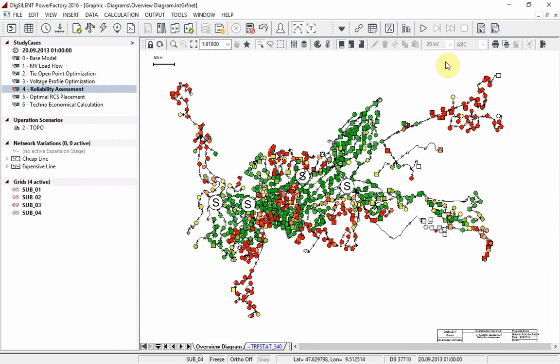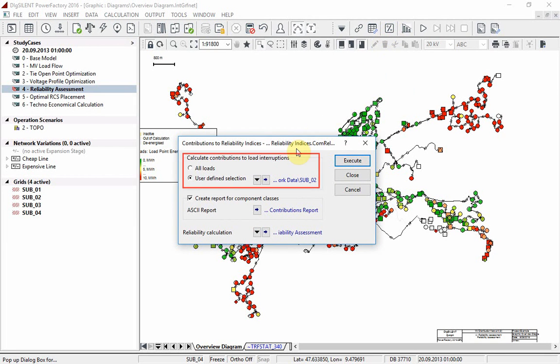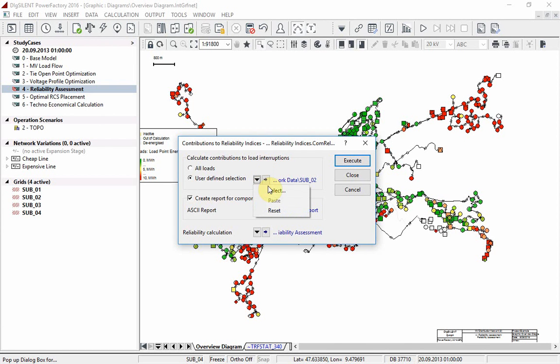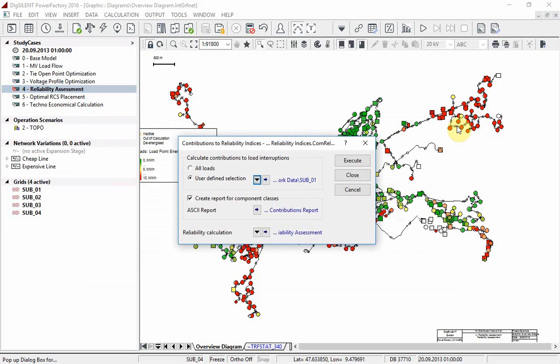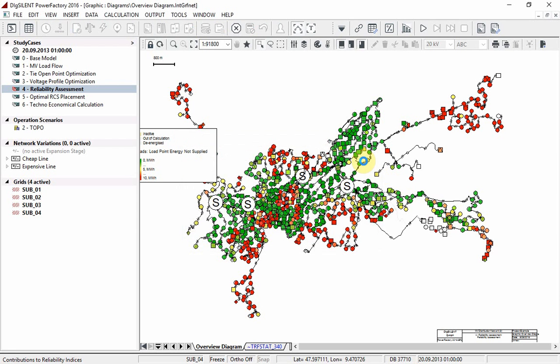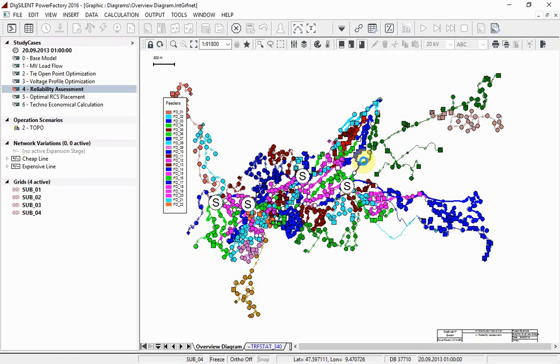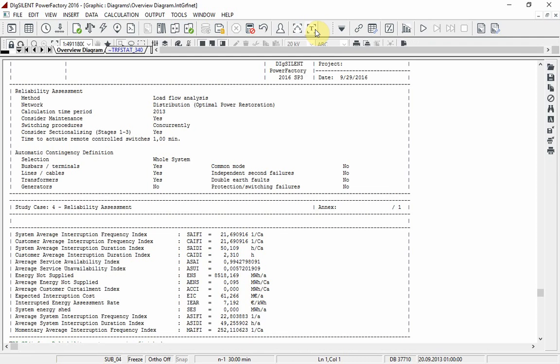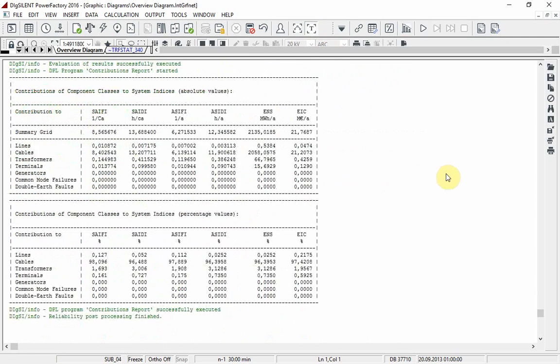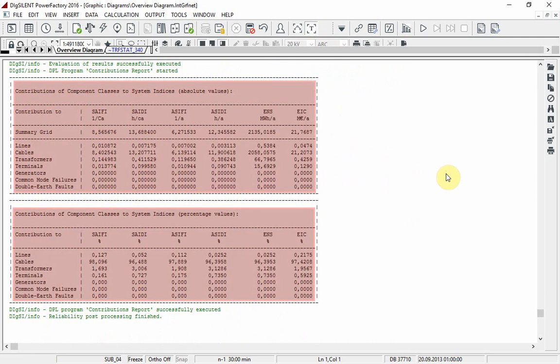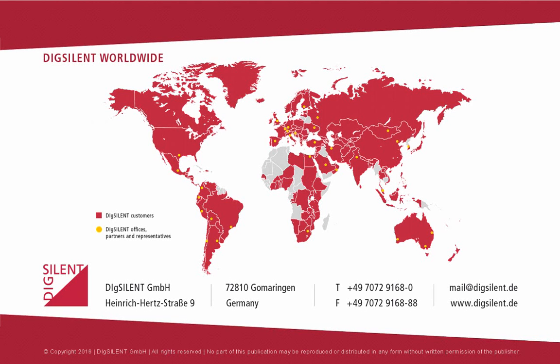We will now calculate the contribution of one grid to the reliability indices by using the command contributions to reliability indices, which is accessible via the reliability analysis toolbox. Select user defined selection and choose one grid. Ensure that create report for component classes is selected and click on execute. The results are shown in the output window.